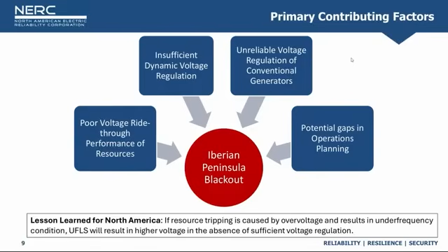Also, then, unreliable voltage regulation for conventional generation. Most of the conventional generation with dynamic voltage control did not act as expected, which was to absorb more reactive power. And of course, by the time they recognized it and started asking units to come online, it was too late. They couldn't get them online fast enough. And we also saw some potential gaps in operation planning. Voltage regulation seemed to be poorly managed here, and it's not clear if they included these oscillations, what they've seen in the past, in their day-ahead contingency analysis for operational planning.